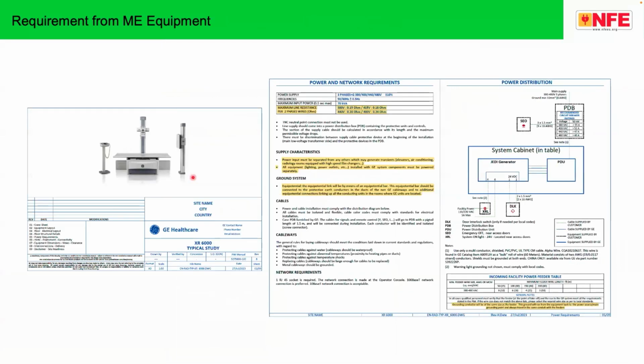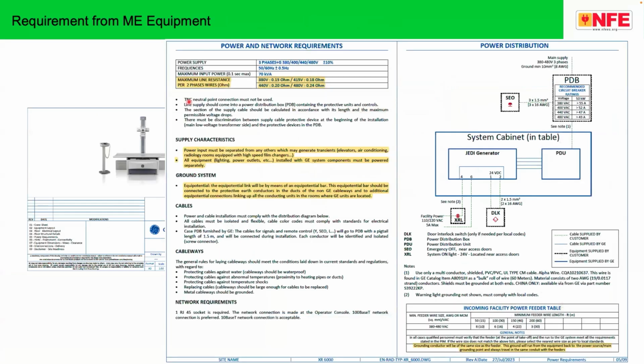Example, you can see here a Siemens, a GE machine. You can see here power supply, three-phase plus G, which means it's a TN-S system because this machine doesn't need neutral. Frequencies, capacity. Now you see one parameter which is very interesting, maximum line resistance. The old name is line resistance, which is already changed to line impedance. So this machine ideally should have, let's say, 415 volt or 440 volt to 0.20 ohm. So 0.2 ohm, 200 milliohm, is the maximum allowed impedance of the circuit for this particular equipment. So ideally, the equipment supplier, while connecting his equipment, is supposed to measure. Now you see the equipment very clearly explains the requirements of earthing and grounding.